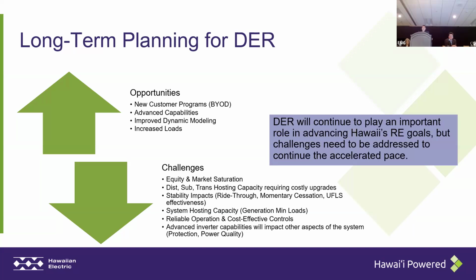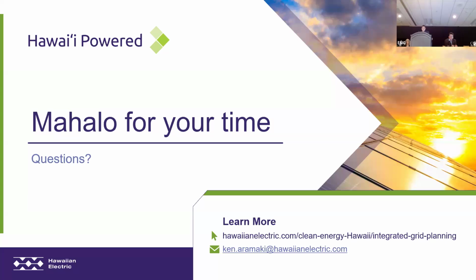We're working on getting a new Category IV under the IEEE 1547 standard. What that does is help keep the DER running at low voltages, and tries to address some of the ride-through issues and momentary cessation. But the unknown is how does that impact protection, en masse protection, power quality, and is the anti-islanding system going to actually work—things of that nature. That's it.